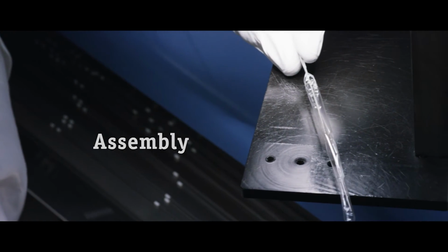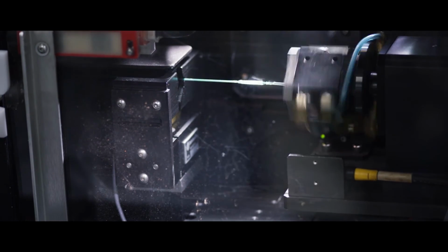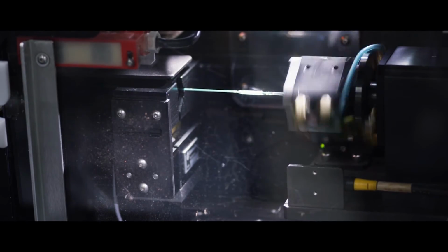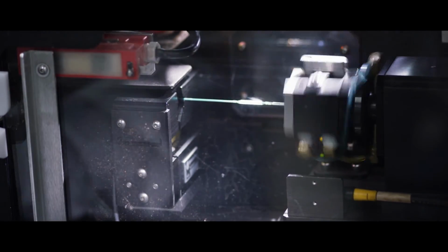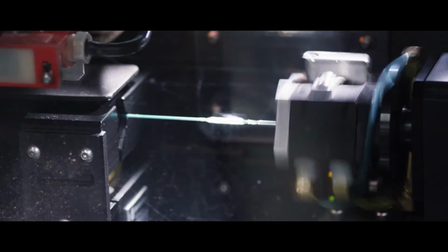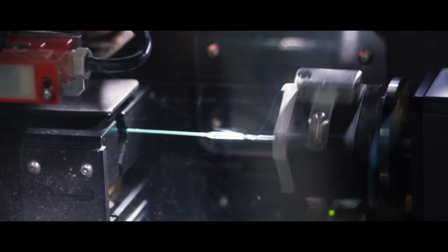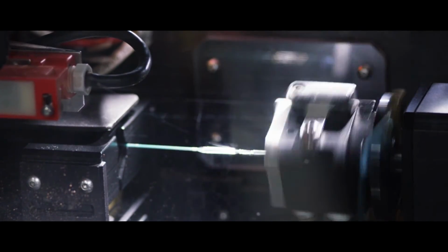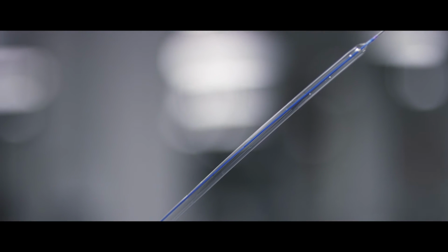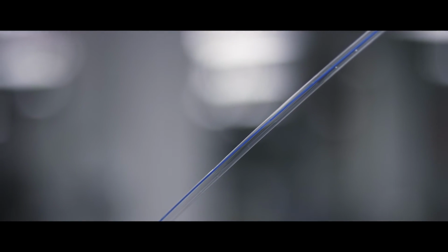Balloon and catheter come together in assembly. While the subassembly rotates, a laser melts and blends the polymers. Heat shrink tubing over the assembly forces the melted materials to flow into precise, low-profile tip shapes typical of our balloons. We're constantly looking for ways to optimize our process.